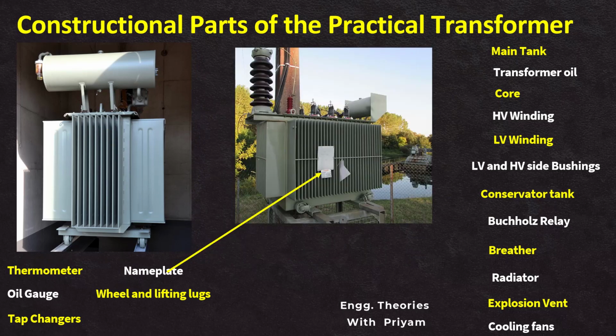The nameplate on the transformer is typically affixed to the exterior of the unit, providing essential information about its specification and operating parameters. Usually located near the transformer's terminal box, the nameplate displays key details such as rated voltage, current, power capacity, impedance, and other critical technical data. It serves as the reference for operators, technicians, and maintenance personnel, offering comprehensive information about the transformer's design and capabilities.